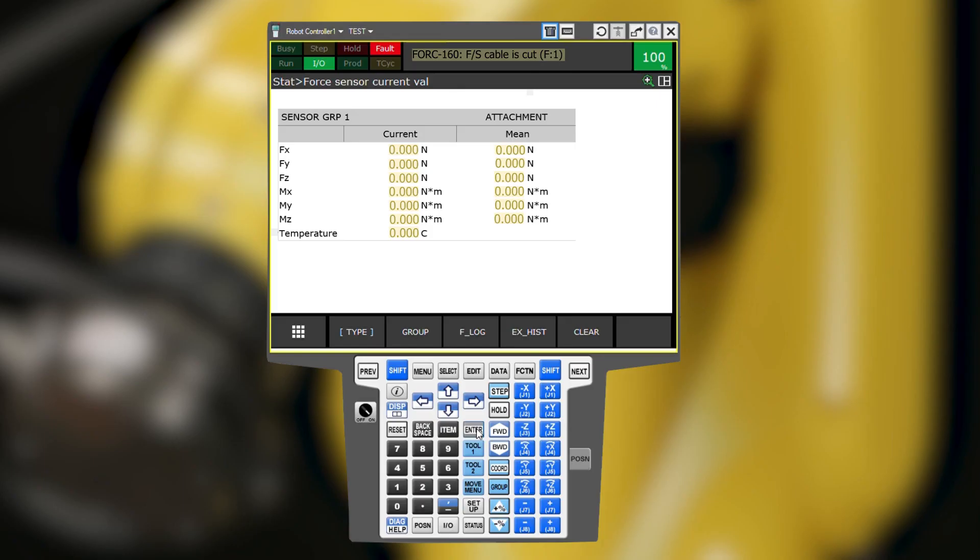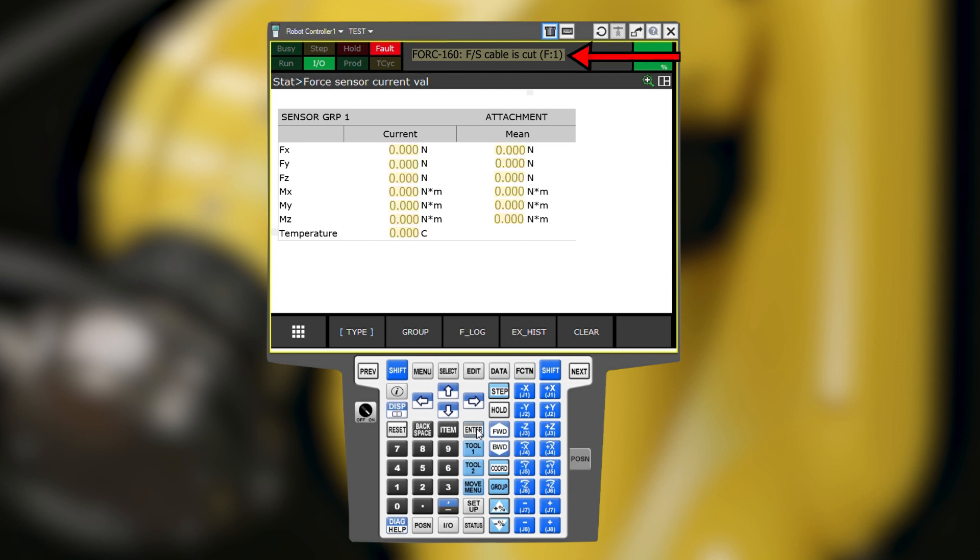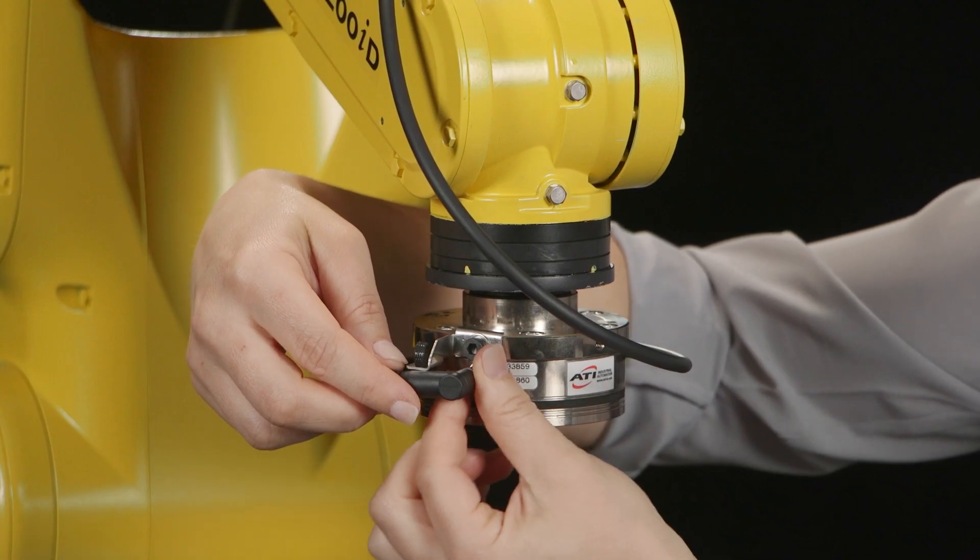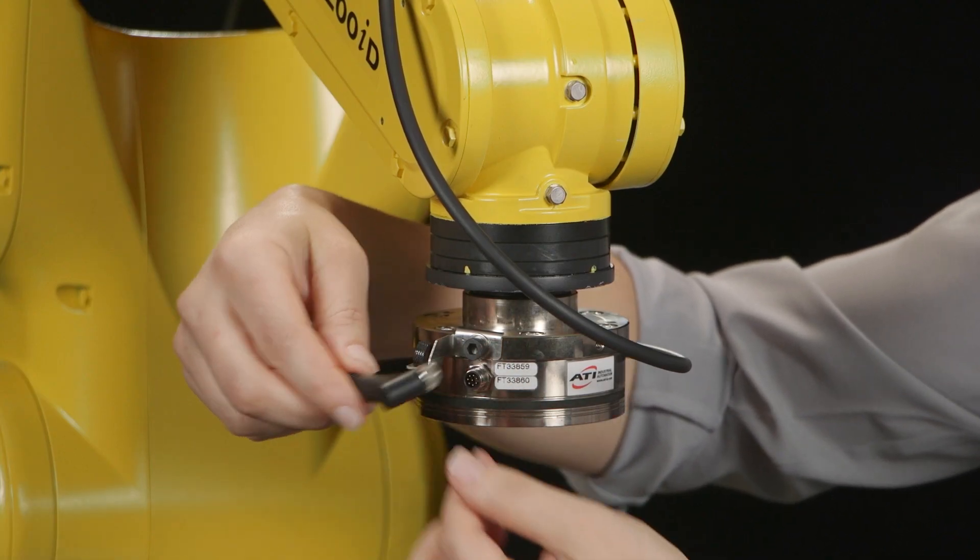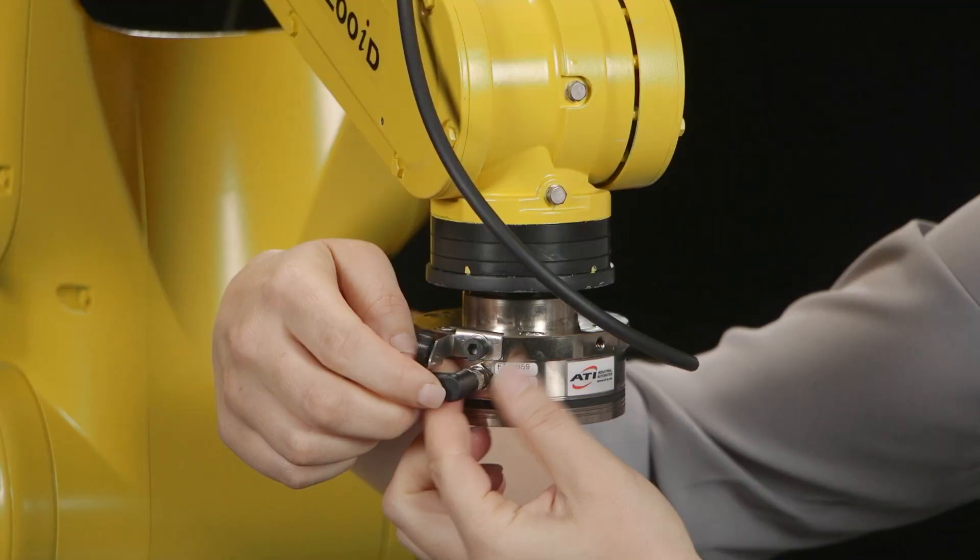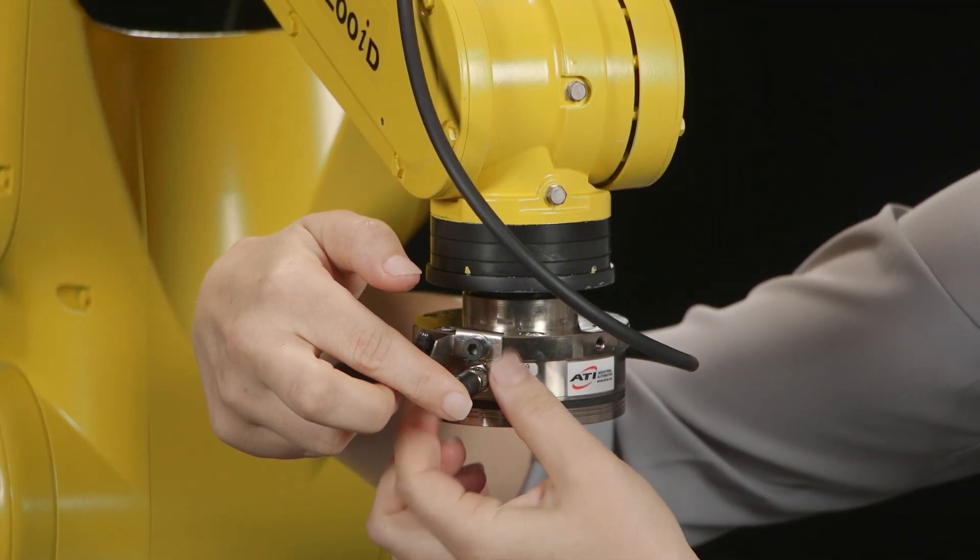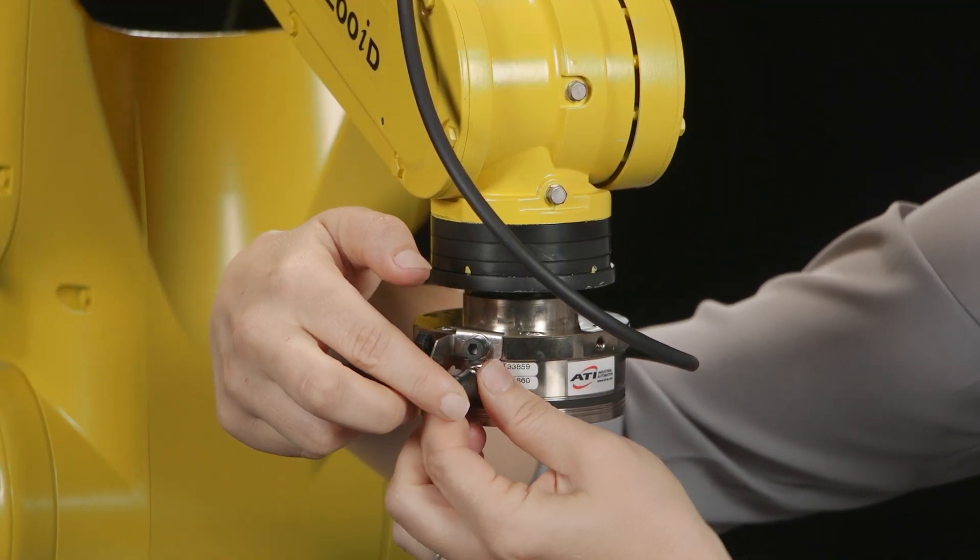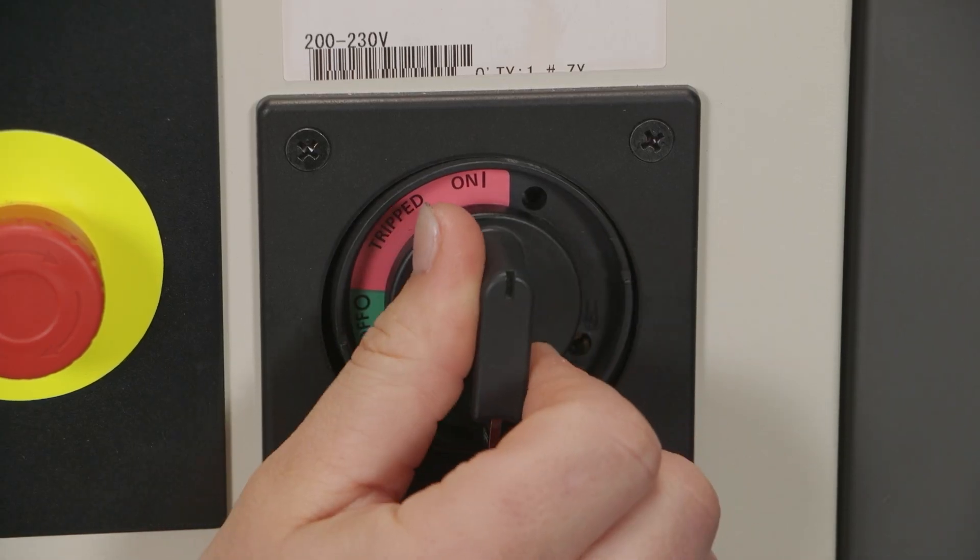If all of the values are a static zero, communication has not been established between the sensor and the robot. There may be an FS sensor cable is cut error, but this is the expected error to display in most communication-related error conditions. Try power cycling the sensor by disconnecting the sensor cable, then turn off the robot controller, then reconnect the sensor cable. Once the green status LED is illuminated, turn the robot controller back on.